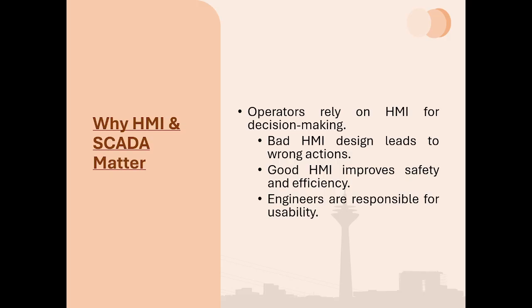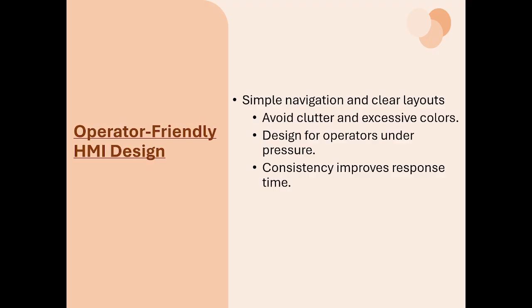So the next logical question becomes, how do we design HMIs that humans can actually use effectively? That leads us to operator-friendly HMI designs. This slide is about designing for people, not machines. Operator-friendly HMI design focuses on clarity, simplicity, and consistency. A good HMI design means operators can understand what is happening within seconds, even under pressure, and it avoids unnecessary colors, animations, and clutter. Good HMI design has clear labels and consistent symbols, so the symbol for a valve is consistent in all the screens. Navigation is simple. But when the HMI design is poor, operators hesitate. And when it is good, they respond confidently.